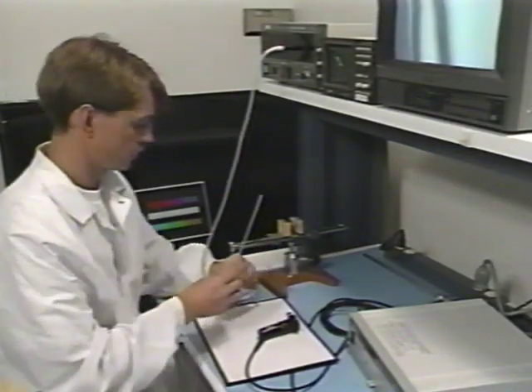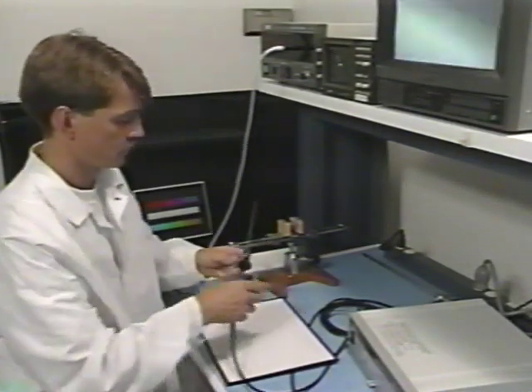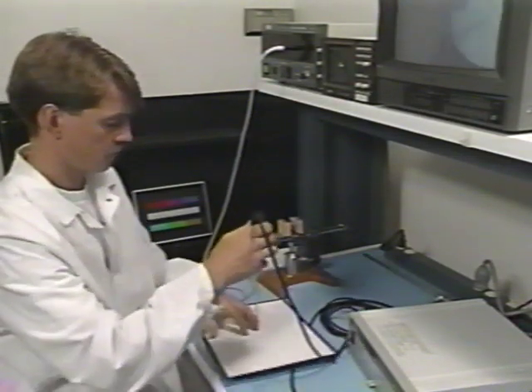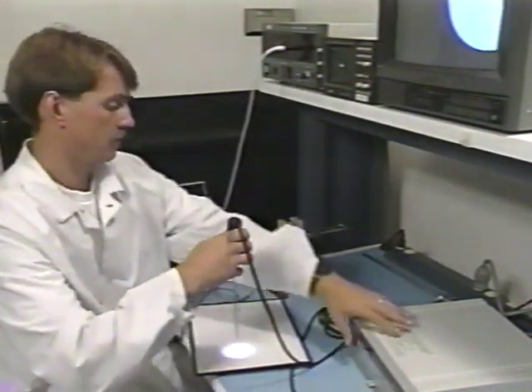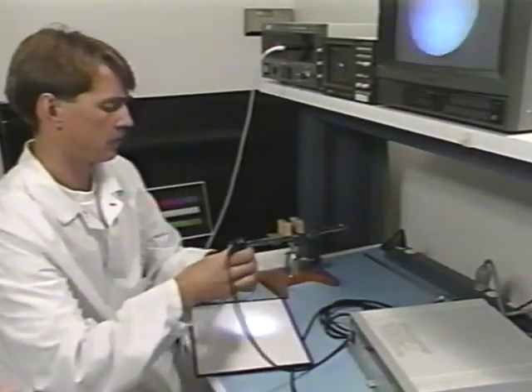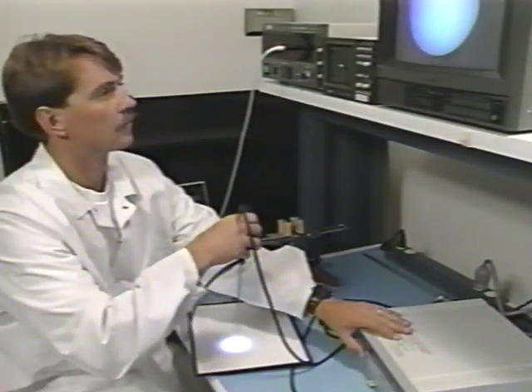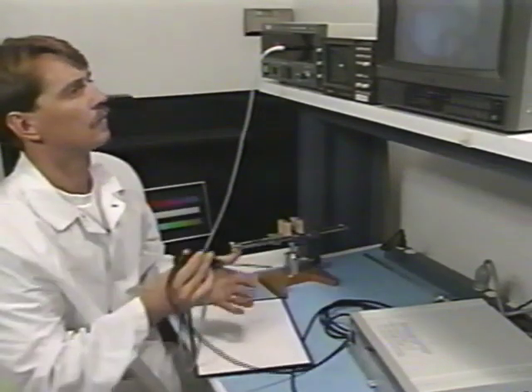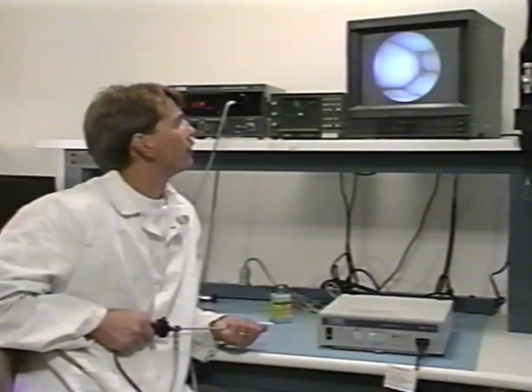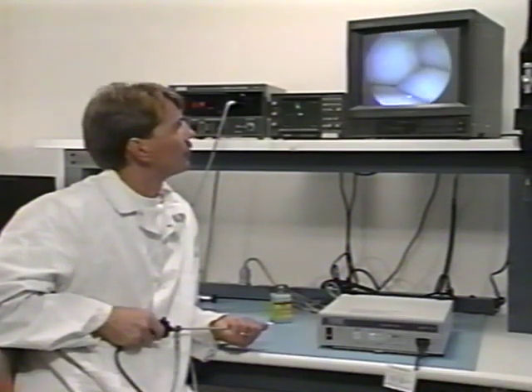Now, add to the system by attaching an endoscope and light guide cable to the camera head. Using the white card, re-white balance the camera with the endoscope attached. Do this by pointing the endoscope at the white card and pressing the white balance button. If done correctly, the same message, "White balance OK," should appear. If the message "White balance failed" appears, repeat the process, ensuring that the white image fills the monitor screen. With the endoscope on, verify focusing and zoom if available.